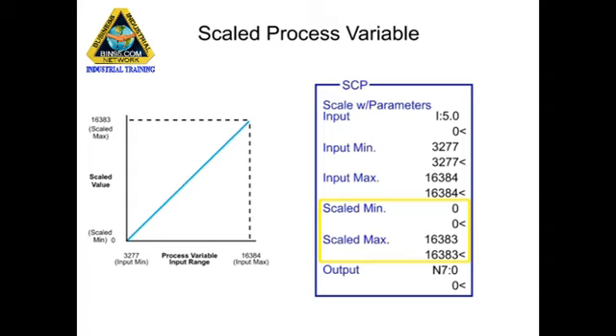The input values are then scaled between the ranges programmed in the scaled minimum and scaled maximum parameters. Scaled minimum value is programmed as 0, representing the low end of the output range. Scaled maximum value is programmed as 16383, representing the high end of the output range. The SCP output parameter is the integer file address where the scaled output is stored and then used by the PID instruction as the process variable.